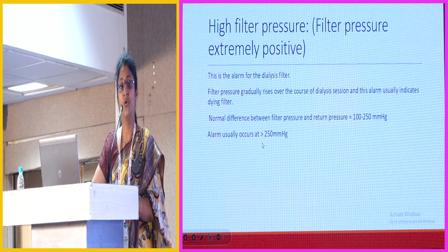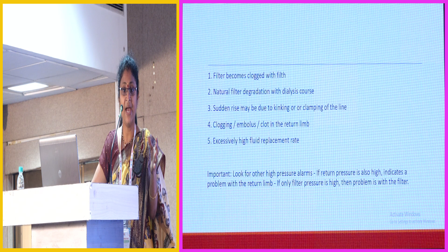The normal difference is 100 to 250, and the alarm comes when it is more than 250 mmHg. The various causes are the filter becoming clogged, or natural filter degradation during the course of dialysis. A sudden rise may be due to kinking or clamping of the line, clotting, or excessively high fluid replacement. We discussed in the morning, if the patient is very hypotensive and we want to maintain hemodynamics, we give more and more post-pump dilution. At that time also your filter and return pressures will be very high. So go and check the fluid replacement. The replacement may be high compared to the filter size or the patient's body habitus.